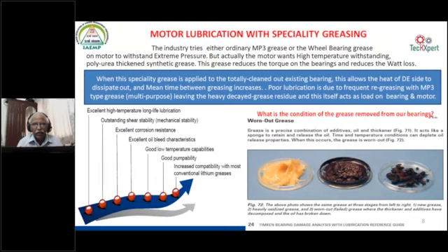What should this specialty grease be like? I'm talking generically, I don't want to give any brand, but generically speaking, it should have high temperature resistance. The industry thought, let us go for wheel bearing grease. Wheel bearing grease is extreme pressure, pressure resistant. But what we need in the motor is temperature resistance. We need a high temperature resistant grease, and it has to have shear stability. Shear stability means mechanical stability against the motor and machine. If it is tangentially driven, the tangential shear stress has to be withstood. Then comes corrosion resistance and oil bleed. Oil bleed means the residue given by the grease, even after it goes beyond its greasing capacity, should be less. Pumpability or penetration length should also be more.